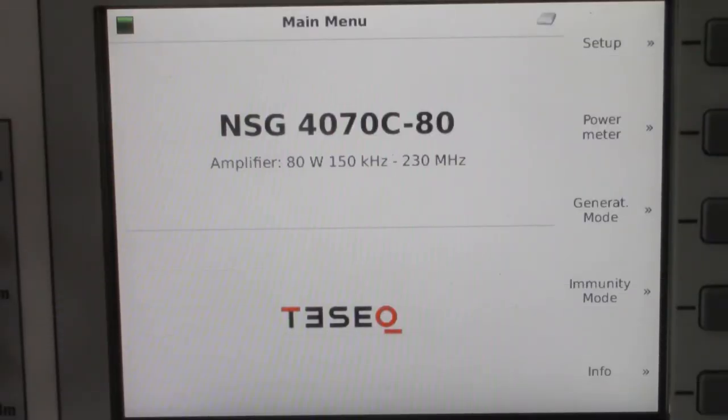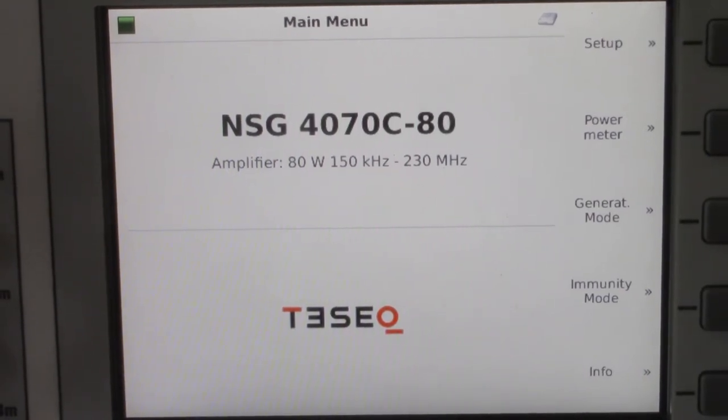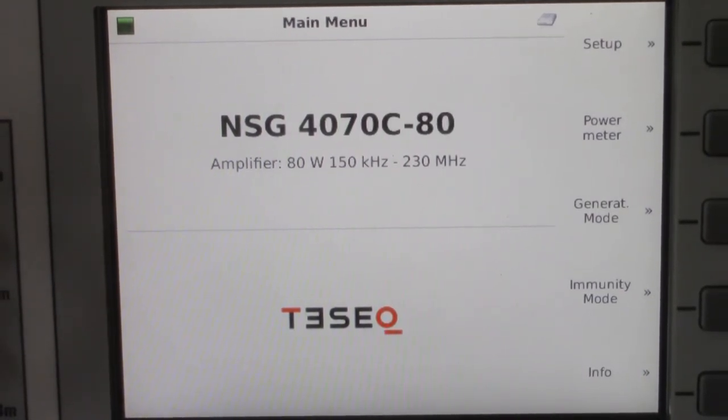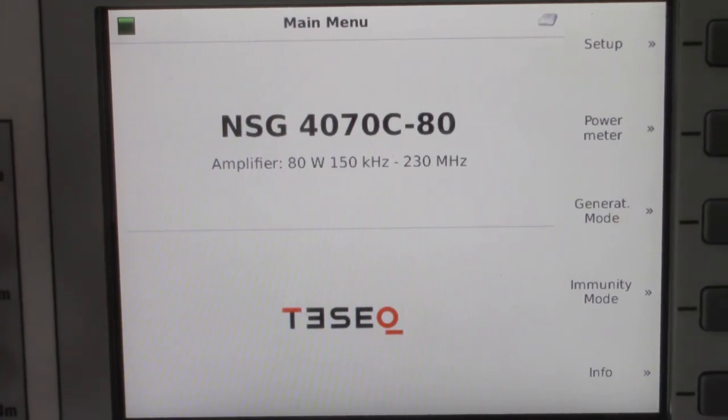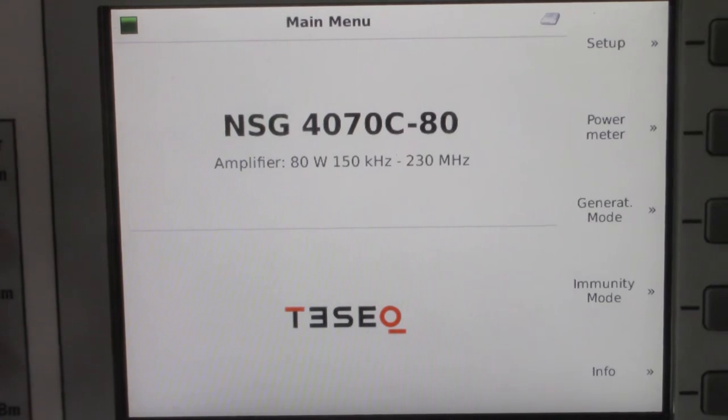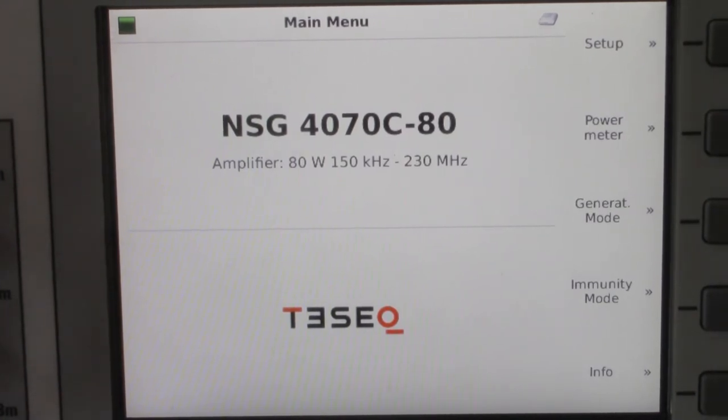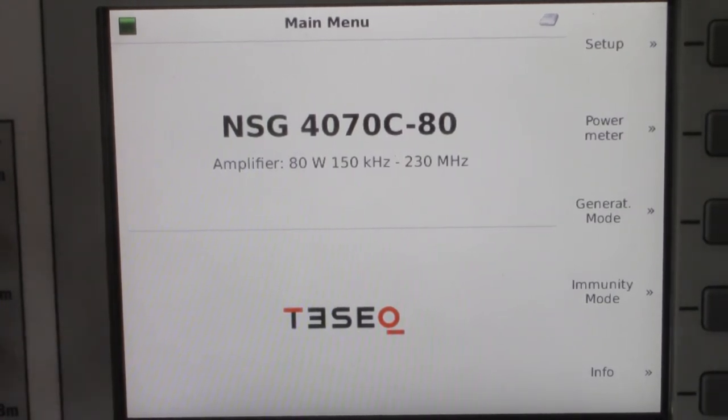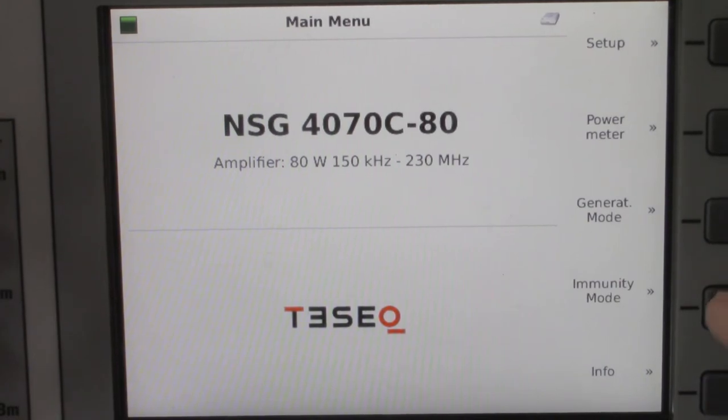As I mentioned before, we're going to walk through how to use the system interface to run that setup for IEC 61000-4-6 calibration for BCI. All we've done so far is made our connections we were talking about previously, and we're going to click on immunity mode.